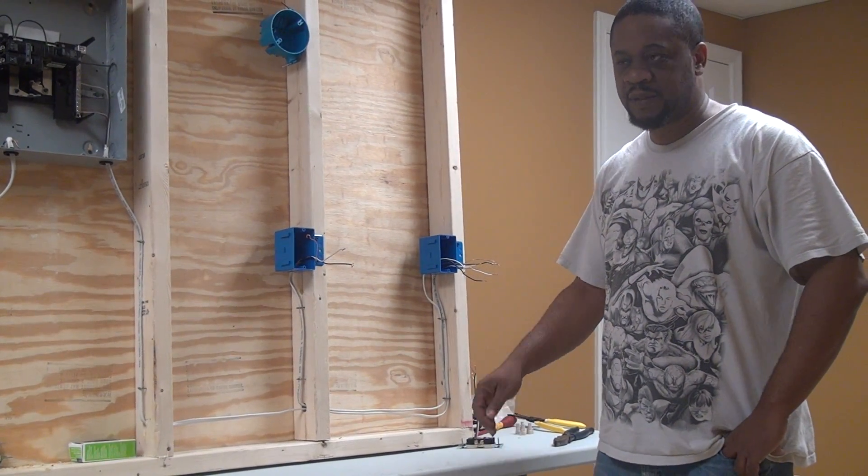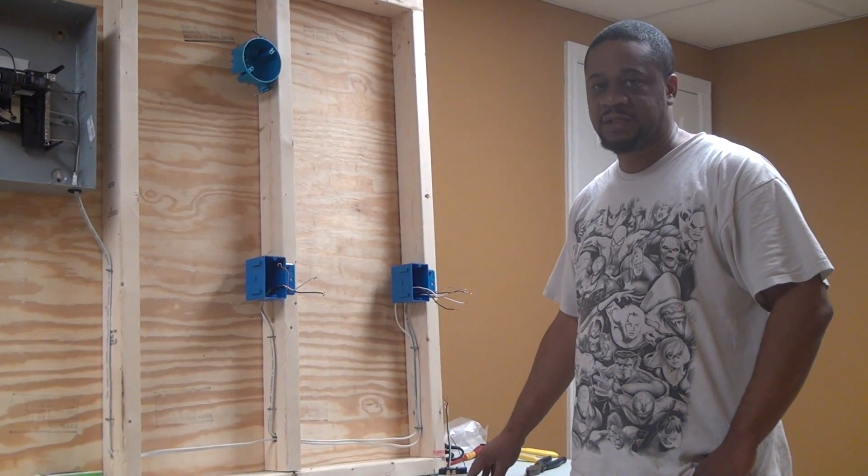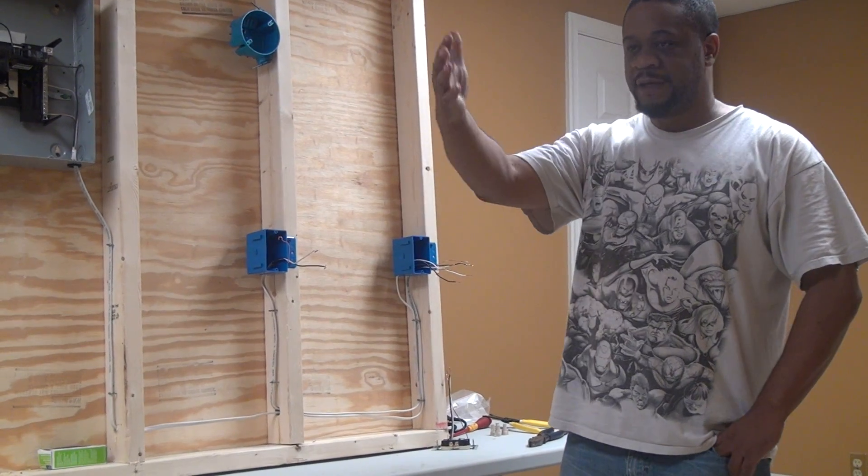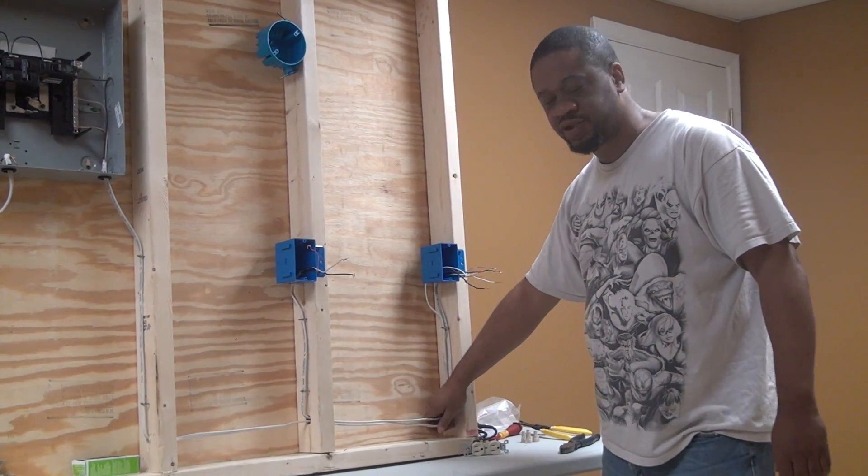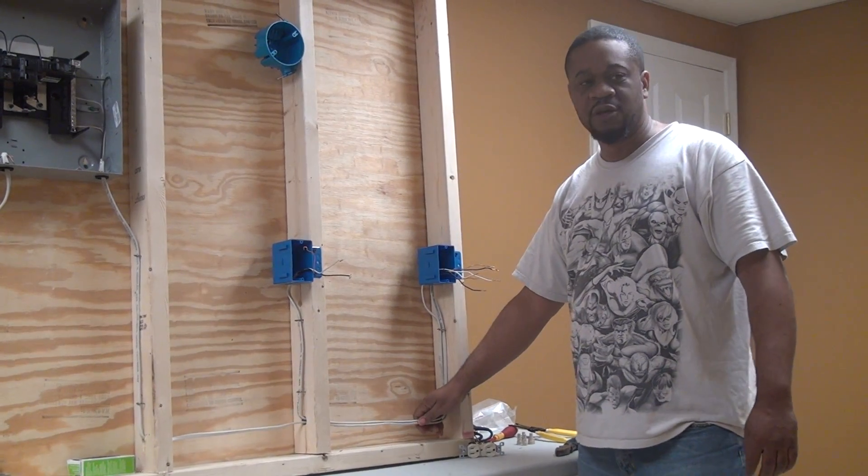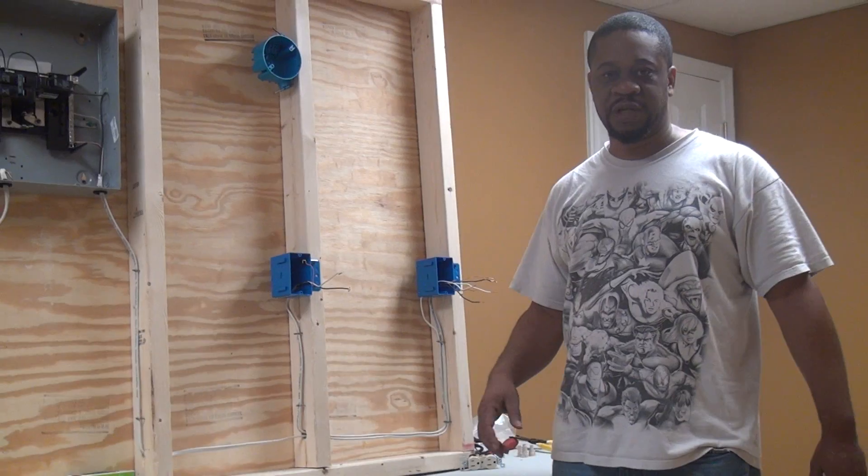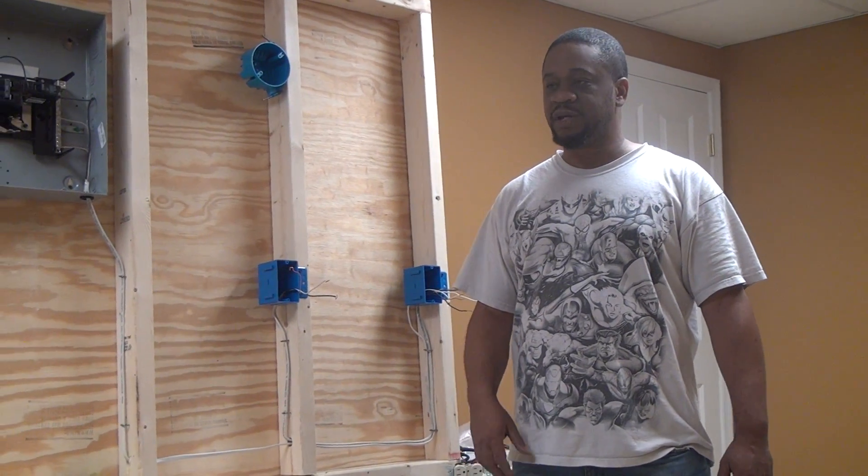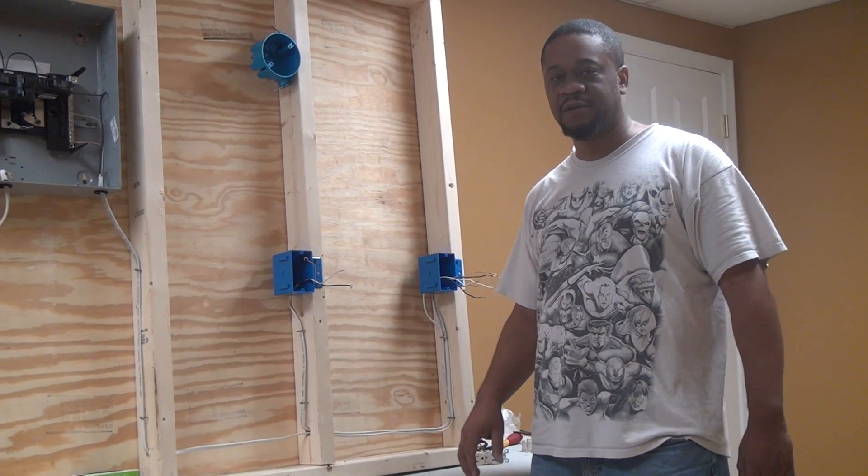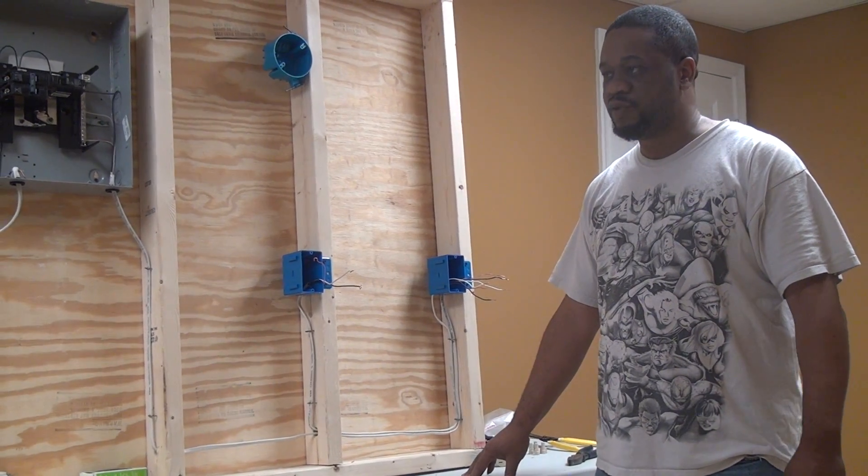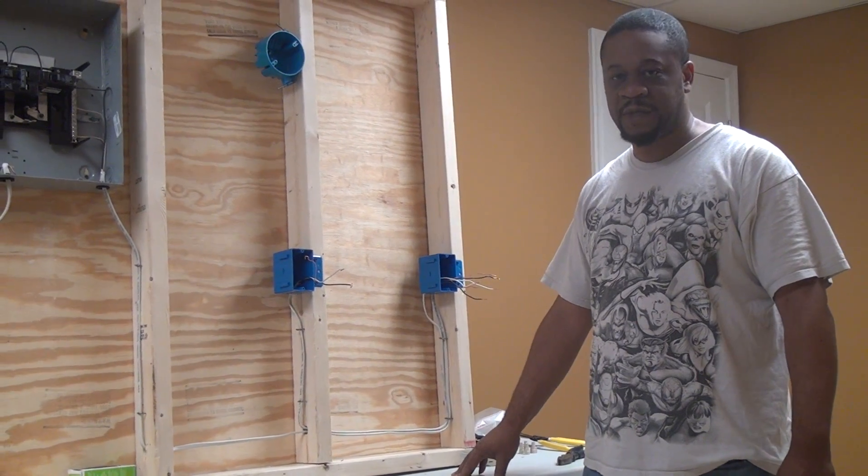That way you exceed the code requirements. The reason for that requirement is that most appliances have a six foot cord on them and it reduces tripping hazards. Anyways, this is not a code lesson. When you're laying out your basement or whatever room you're doing, you want to make sure that your outlets are no more than 12 feet apart and you want to have one within six feet of any door.